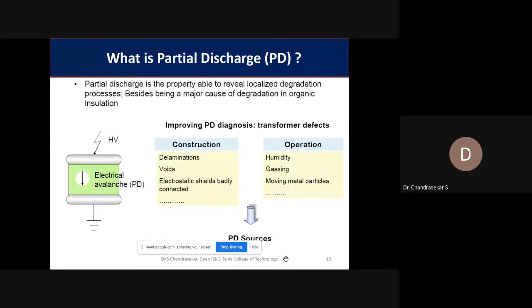cavities or voids. Okay, so there it will easily break down, because since the voltage is very high, the bubble is simply filled with air. The air has a very low dielectric strength when compared with the oil, and therefore the air will simply break down. So it will create a discharge inside the oil. If there are so many bubbles or cavities forming inside the oil, then it will lead to so many discharges at different places. So this is simply an arcing. A partial discharge is simply a small arc happening inside the insulation.